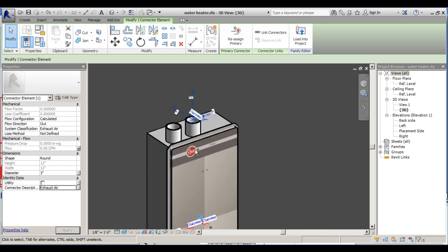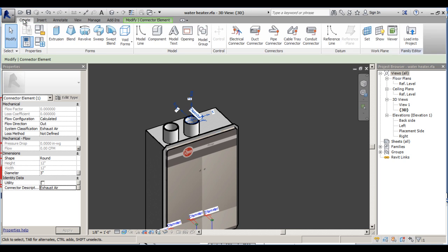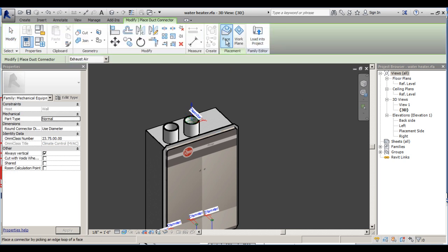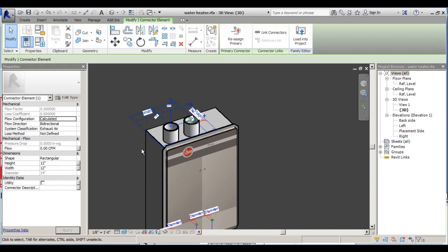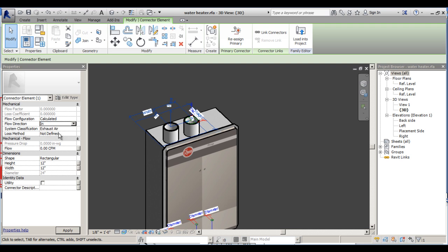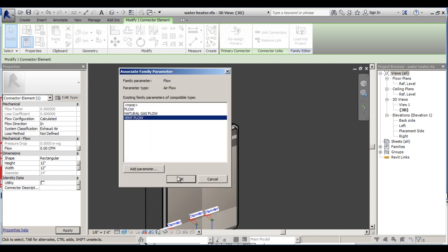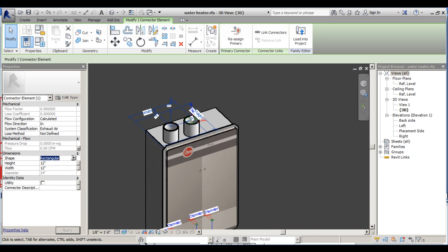Go back to Create, choose duct connector, set to face, and click the top face of the second pipe. Click on the connector and set parameters: flow direction is in, system classification is exhaust air, loss method not defined. Set the vent flow property for flow. Shape is round and diameter is a three-inch pipe again.